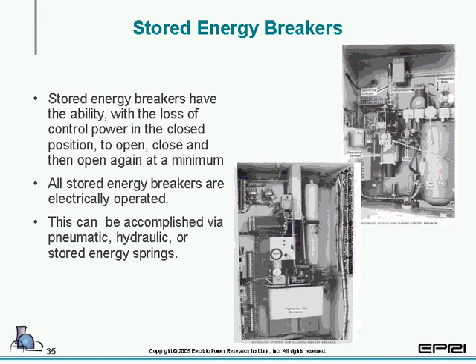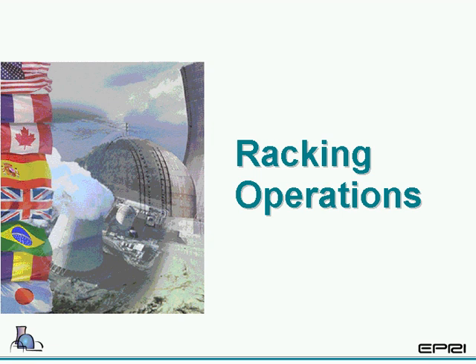Last I'm going to take a look at is stored energy. Typically, most people consider stored energy to be spring-charged designs, but there are many other designs of stored energy. Several of which we have here are accomplished by pneumatic, hydraulic, and of course, most common is the spring charging. And that picture's not shown. And that's pretty much it as far as the breaker's concerned, the different types. Next we're going to take a look at the racking operation.